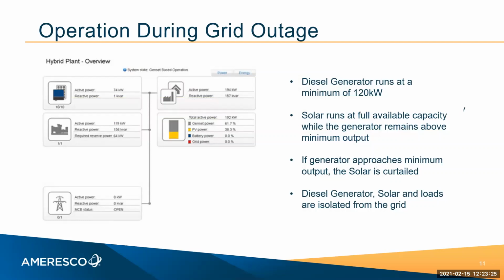So the diesel generator is set, and it shows required reserve power 64 kW on the left. This was during commissioning, so that wasn't the final set point. But the diesel generator runs at a minimum of 120 kW, and that's to protect the generator. As long as the diesel generator is above 120 kW, the solar array would be allowed to output at full capacity to meet the demand of the building.